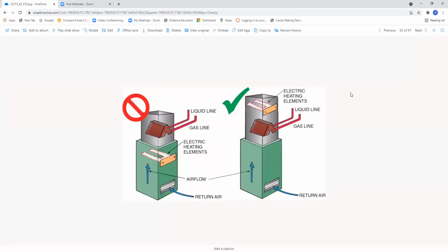Okay, in this case, it shows electric heating elements of the air handler, return air. Here we have the refrigerant vapor liquid on the evaporator coil and the A coil above here. Now, what's wrong with this picture? What is wrong with that picture? Okay, look where the heating elements are located. The heating elements should never, never, never be installed below the evaporator coil. Okay, in this case, this heating element needs to be installed above.